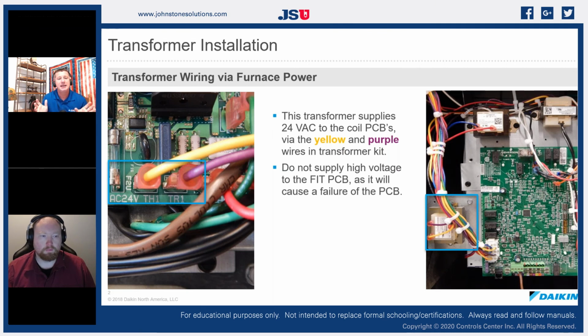So if we look at what we're doing electrically, we really have to understand how we're communicating. Because when we were talking about a 24-volt AC, a legacy style communication coming from a thermostat, not really talking but making switches for our equipment, we were just sending out 24 volts AC, and it was making some kind of an action. It was turning on some type of a switch, contactor, whatever it was. So we were applying a load on those two wires, right? If we just had 24 volts going to a contactor, we had common on one side of a contactor, and we had our 24 volts AC feeding the other side. And it didn't really matter which way the current flowed.